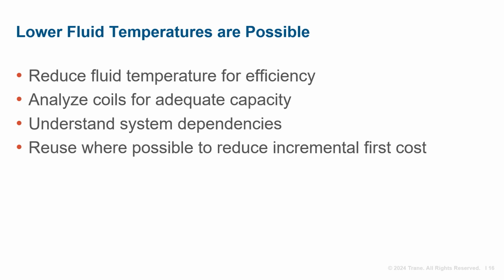In summary, it's certainly possible to retrofit existing hydronic heating systems to accommodate lower temperature heating fluid to maximize system efficiency through careful system design practices to enable efficient equipment operation. Reuse of coils is possible, even if flow rates increase, provided piping is adequate for increased flow rates for various terminal and air handling devices. Now let's discuss a few system options that are prevalent today.